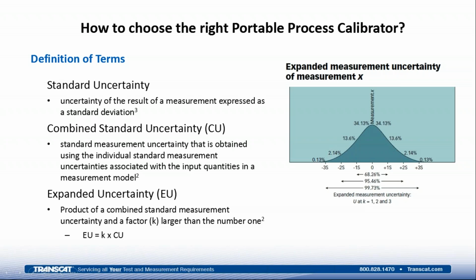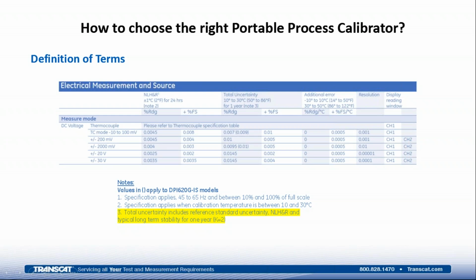So where does this come into play when we're actually looking at the specifications on a data sheet of a calibrator? I've included an excerpt from our DPI 620 Genii handheld multifunction process calibrator. You can see that in the specifications there are several different columns. The one that I would point to is the total uncertainty column, which is defined in a higher level of detail in our notes below where the specification is given. Our total uncertainty includes the temperature range over which it's defined. It includes the stability or instability over a 1-year period. It also includes the uncertainty associated with our reference standard that we're using to calibrate it, the nonlinearity, hysteresis, and repeatability, and as I said before, the typical long-term stability for 1 year with a K factor of 2.